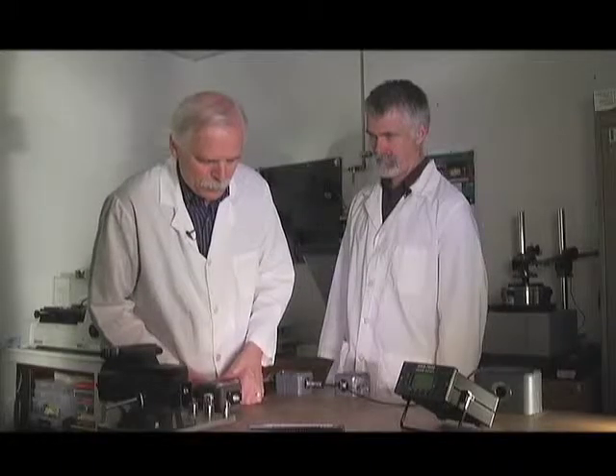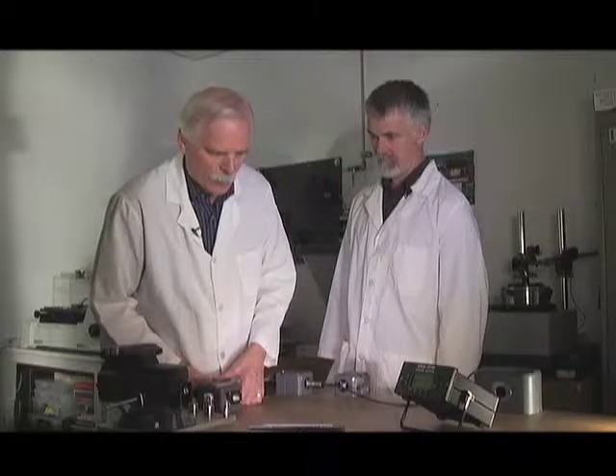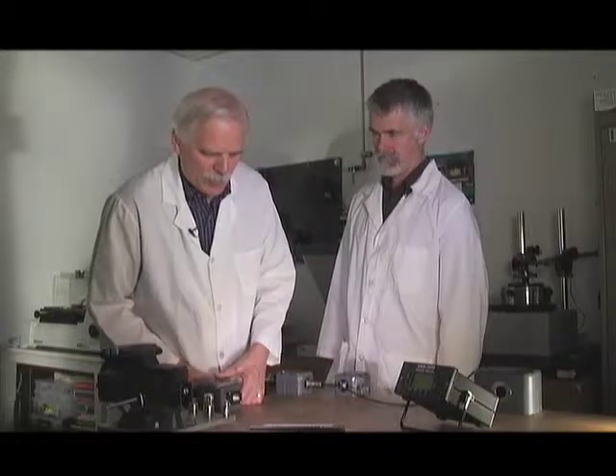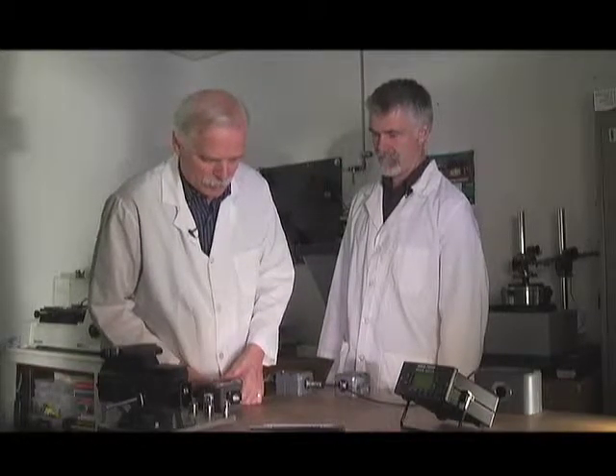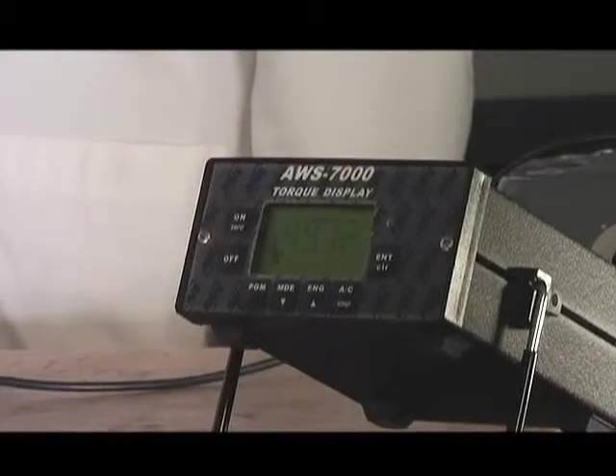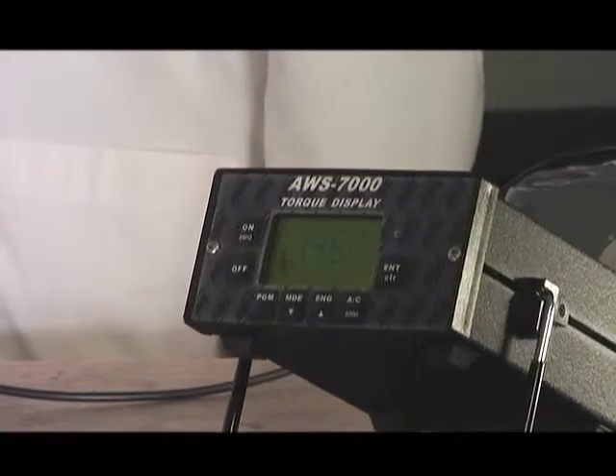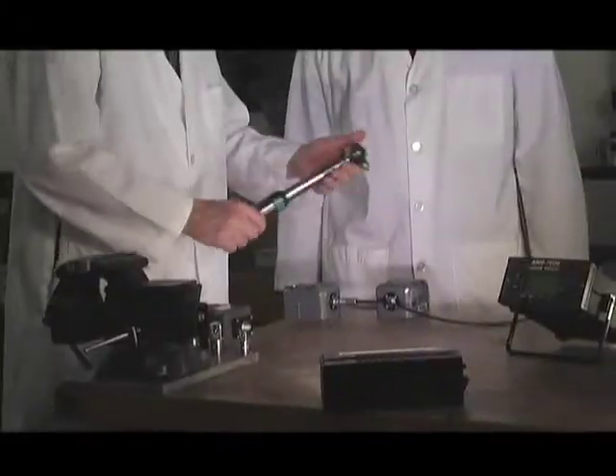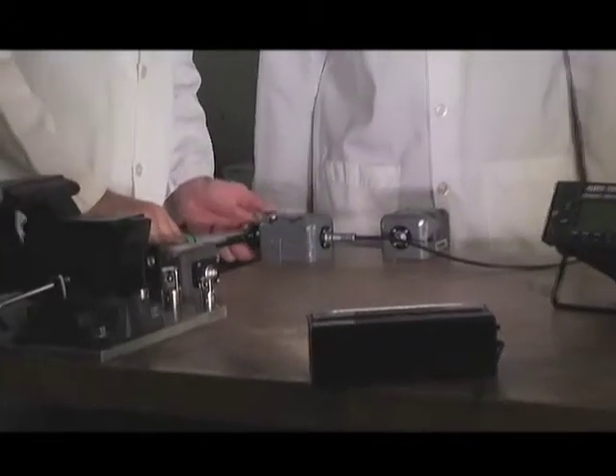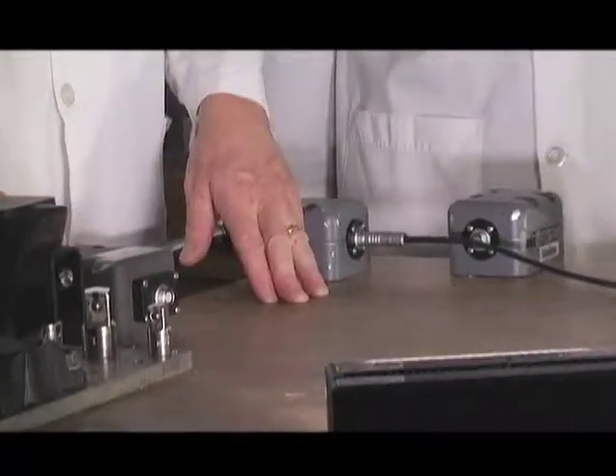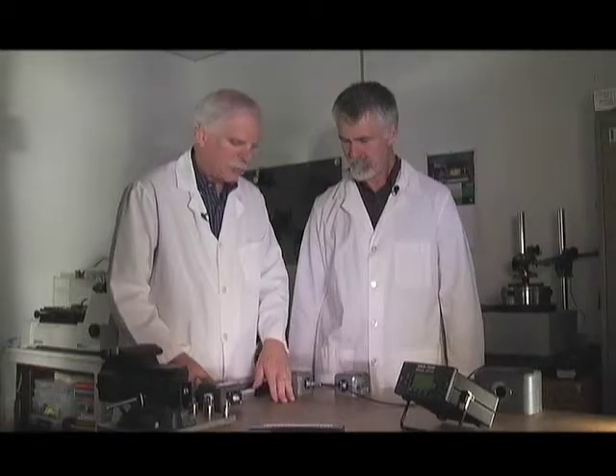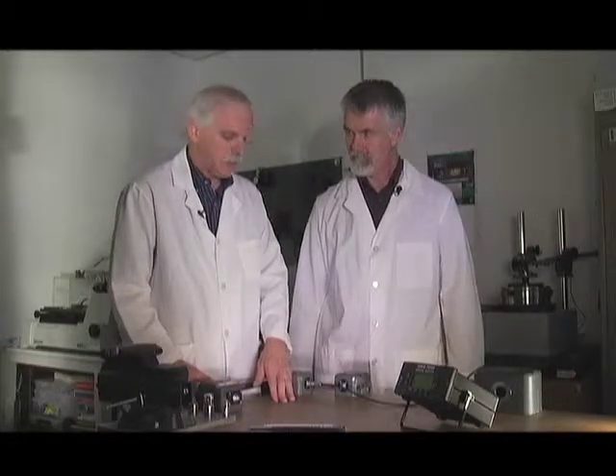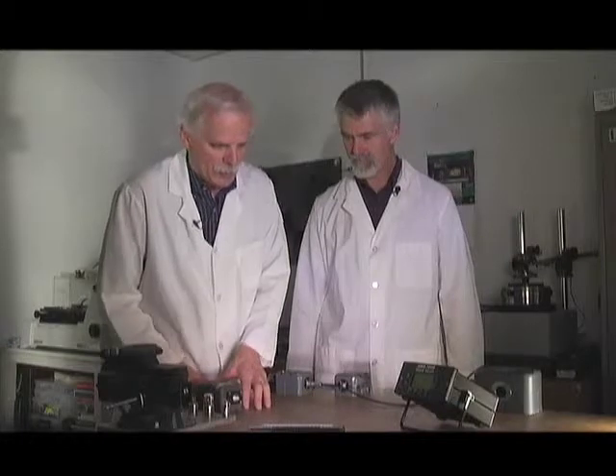And we'll click it a few times and we'll see what we get. 49.41. 49.37, 49.72, so staying right in the 49 range. Okay. We would average. We typically will do 4 or 5 clicks and average the readings. Okay. Now we're going to set it to 100 inch-pounds, and we'll take a series of readings. And the tolerance on this with the 4% would be 96 to 104. It has to read somewhere in between there.